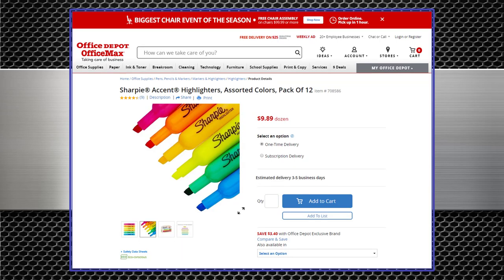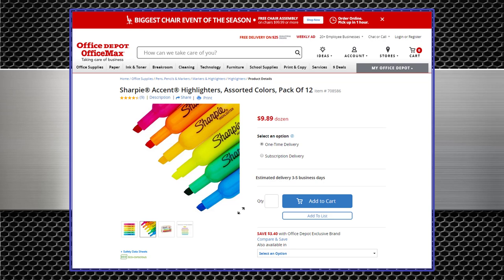Highlighters. These are great for highlighting notes on drawings that you don't want to miss during the takeoff. I generally use a yellow highlighter to highlight critical installation methods in the plans or specifications. For instance, sometimes the specifications require a minimum of three-quarter inch conduit or that you increase wire size on 20 amp circuits to number 10 copper over 60 feet in length. I also use it to highlight special notes on individual drawings that I want to be sure I address in the takeoff. I use an orange highlighter to highlight the specific types of permitted material like EMT, MC cable or GRC just so I can remember the flavor of the takeoff for quick reference.